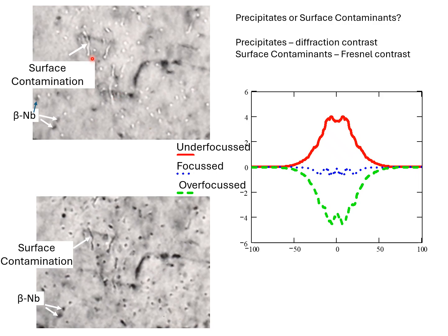Especially if you see it in a wormy kind of structure like this, it is more than likely contamination in cases where you don't expect cavities. So if you have a sample where you don't expect to see a cavity, and there is something that looks like a cavity, check it out, do some stereomicroscopy, and verify for yourself that it is within the foil and not on the surface.